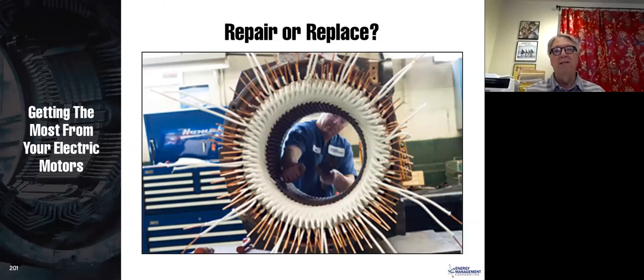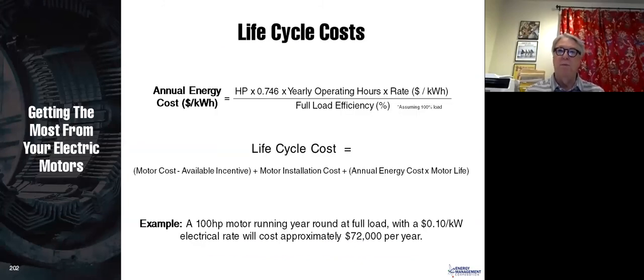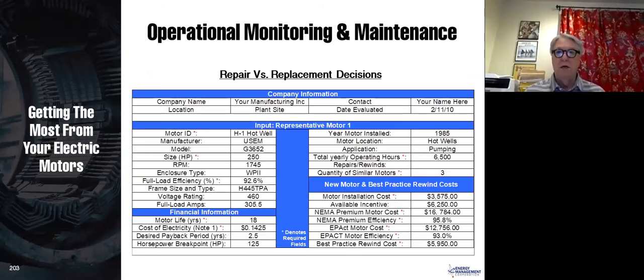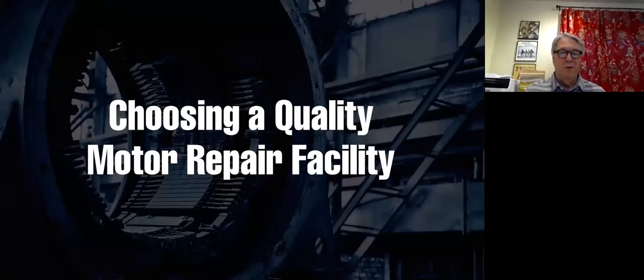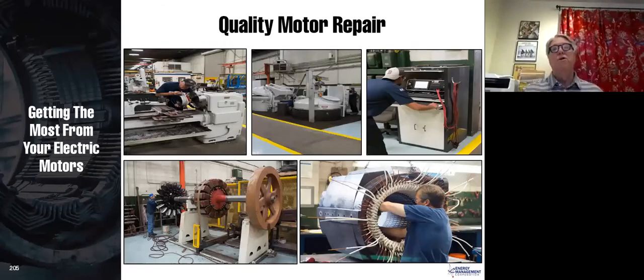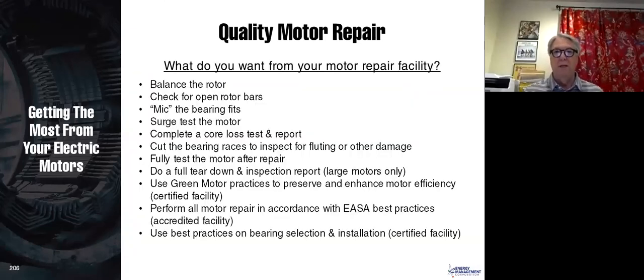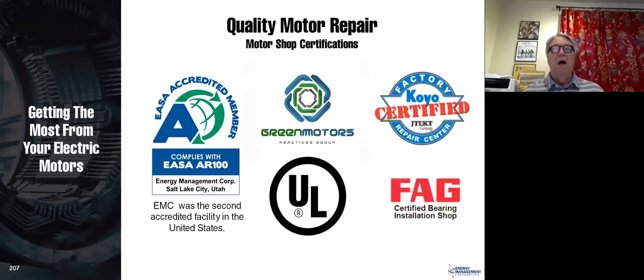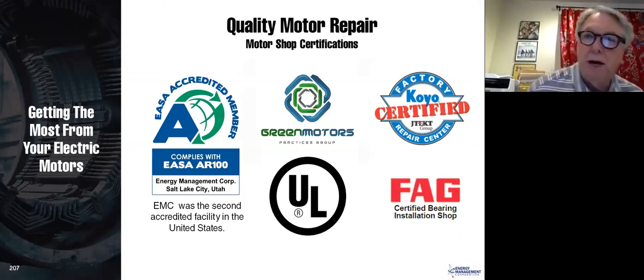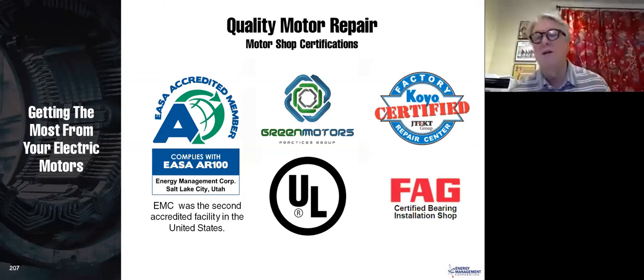Repair or replace, your motor shop can tell you that. Typically, we look at 50 horsepower, but it depends on the size. This is your life cycle costs, all of which is in the book. And I'm sorry I'm going through this kind of quickly. Make sure you use a quality motor repair facility, and these are the things you want to check with your motor repair facility. These are certifications: EASA, Green Motors, UL, and bearing certification facilities.